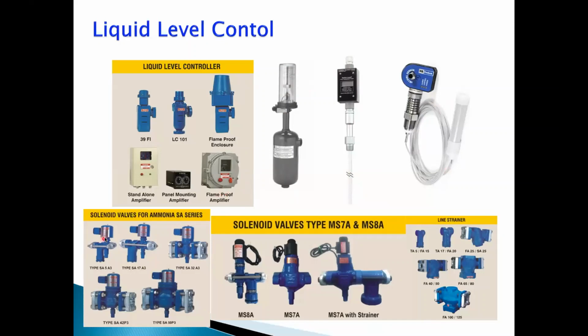The solenoid valves, liquid line solenoid valves: you have direct operating solenoid valves, or also you have pilot operated solenoid valves. Direct operating means that when you give a supply of 230 volts, the valve will open. It will lift the plunger, and in smaller valves the port will directly open. For larger valves, when you give the supply, the pilot valve will open and the inlet force will force the piston to open, and liquid will pass through.